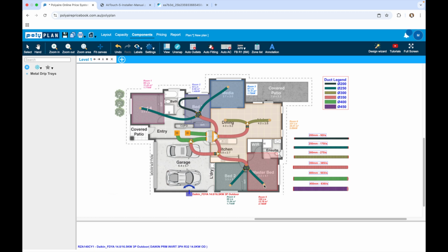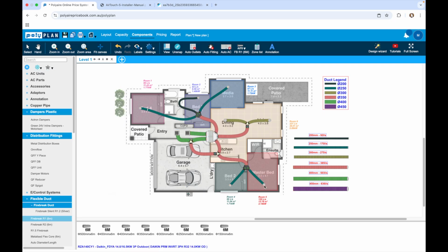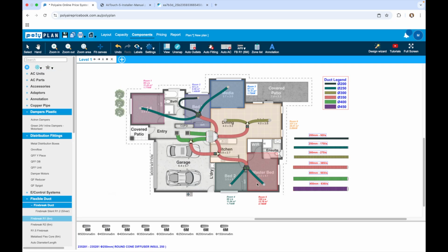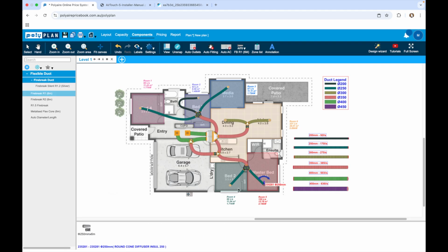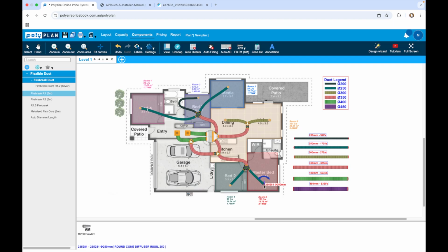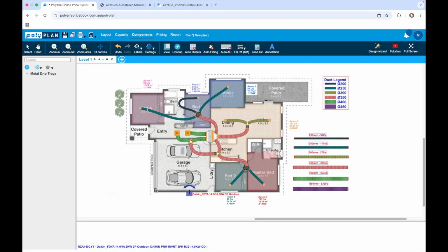So if this room gets to 20 degrees and this was to go off, this wouldn't start again until this room gets up to 22, 23, maybe even 24 with some brands. By the time that does start to happen again, you start feeling uncomfortable in here. Ideally you want to get this room to 20 degrees and maintain 20 degrees. Maybe a degree is fine, but if you've got big variances, it's going to feel uncomfortable, and it's also increasing the amount this stops and starts.